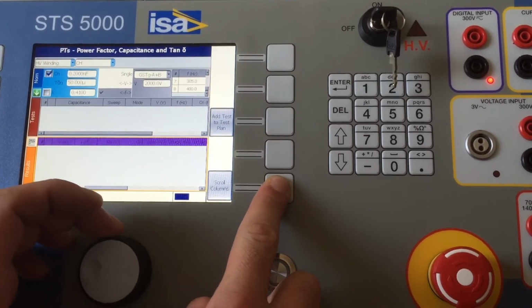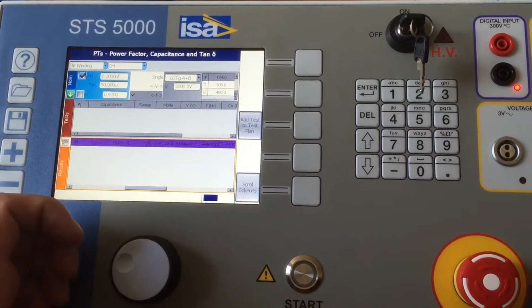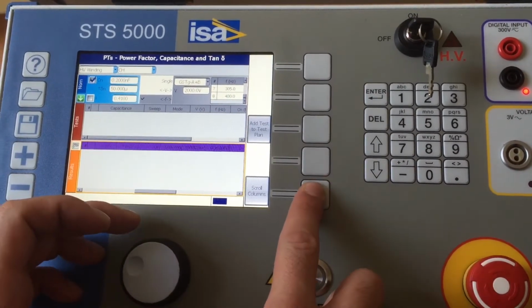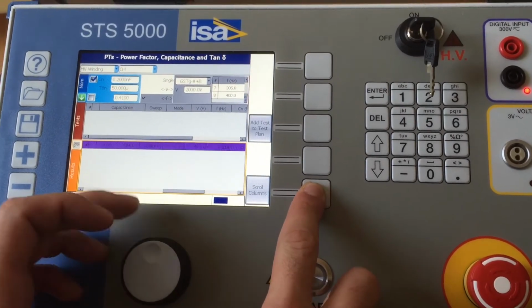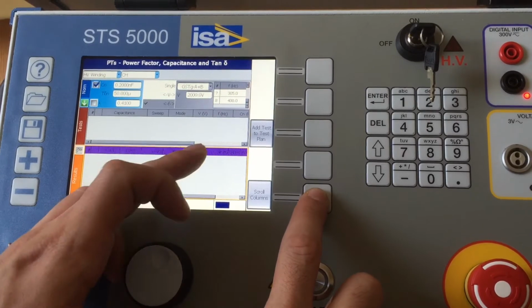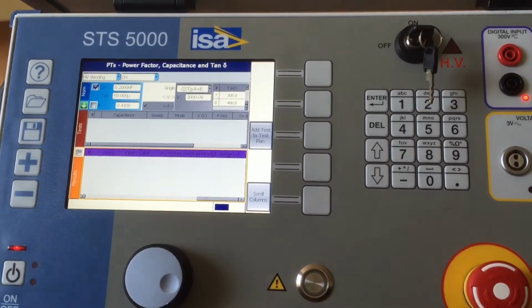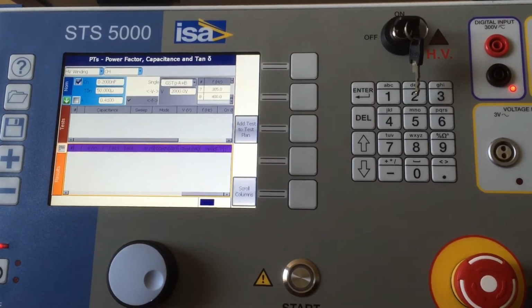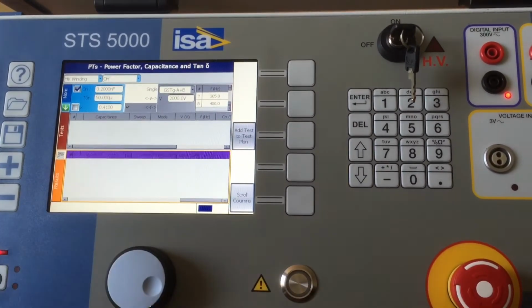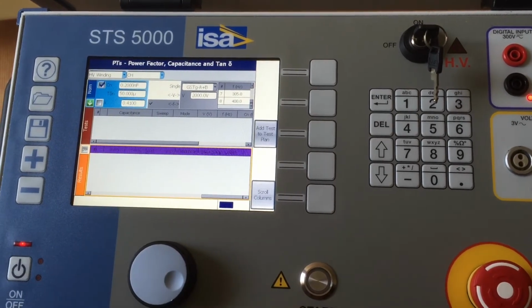You see a lot more information. So if you were to test a circuit breaker for tan delta, you would be looking at this information here: the actual losses, and you can also see the actual capacitance and actual impedance. And this is basically the place where it tells you how much the angle you measured differs from 90. You can also get the reactive power and the apparent power and some other information.